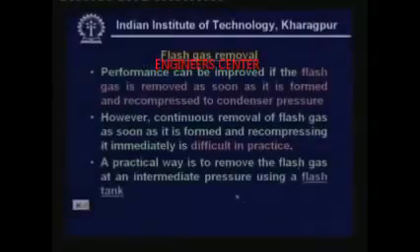pressure evaporator gas. One thing you can see is that if you don't have this flash tank, the quality at the entry to the evaporator would have been 9 prime. By using the flash tank you could reduce the quality considerably. So you can see that at the inlet to the evaporator, 9 has more liquid than vapor compared to 9 prime. So this is briefly the working principle of a flash tank.